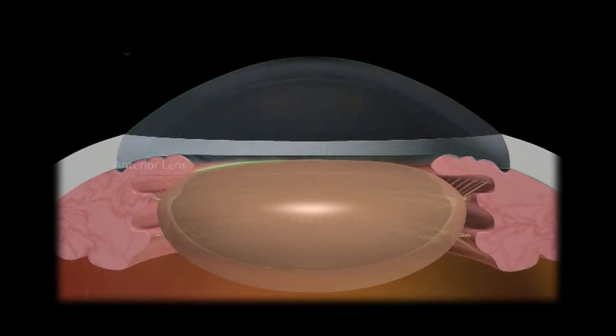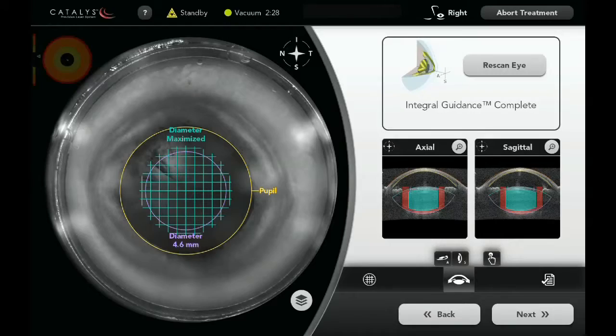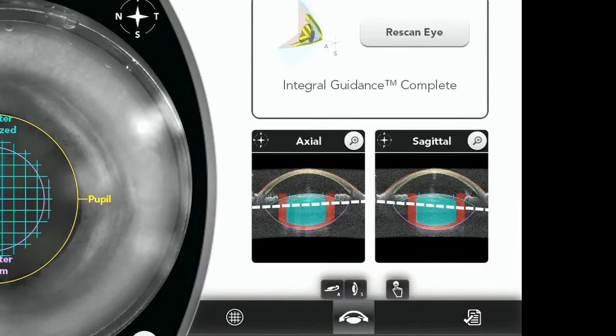The third step is visualize and customize. The Catalys system's integrated video and 3D spectral domain OCT visualize from the anterior cornea through the posterior lens. Sophisticated algorithms automatically customize the treatment plan in 3D. Together, the process is called integral guidance. With integral guidance, Catalys automatically centers the capsulotomy on the pupil, limbus, or scanned capsule. The system can detect ocular structures and customize the treatment plan even when the eye or the lens is tilted relative to the laser path. Integral guidance also optimizes the lens fragmentation depth by fragmenting deeply while maintaining adequate distance from the posterior capsule.